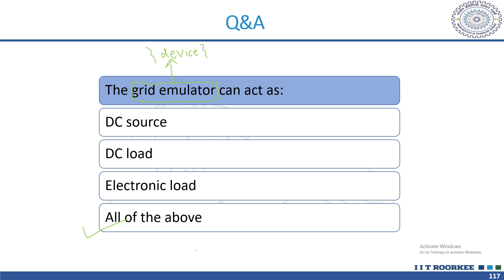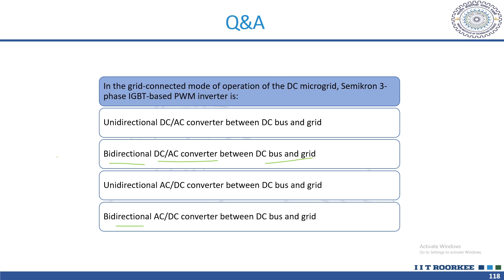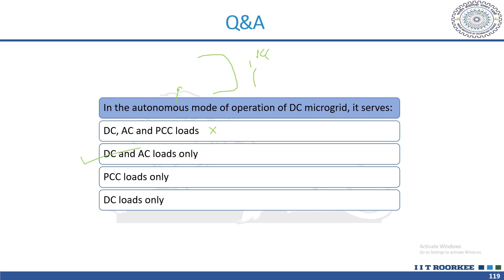Then in grid connected mode of operation, the DC microgrid, this Semikron IGBT stack is what? So it will be bidirectional, right? And it is an inverter, so it is a DC to AC converter between DC bus and the grid. So it is B. Then in autonomous mode of operation, the DC microgrid, it serves which of the loads? So autonomous means this switch, yes, so the switch at the PCC is open. So PCC loads it cannot supply. And within the DC microgrid, we can also have AC loads which are connected through converters. So it is both DC and AC loads.